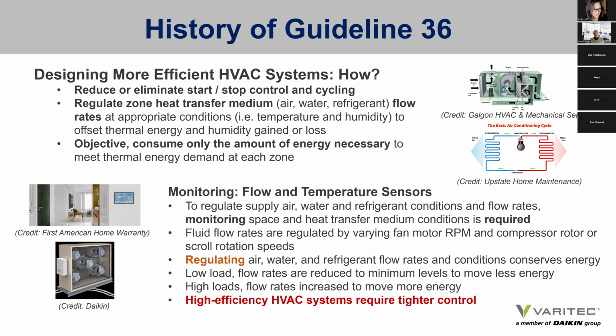You need to monitor the temperature of the space that could require cooling or heating, and you have to monitor the flow of heat transfer medium to those spaces so you don't overcool or undercool or overheat and underheat the zone. So to regulate supply air, water, and refrigerant conditions and flow rates, monitoring space and heat transfer medium conditions is required. Fluid flow rates are regulated by varying fan motor RPM, or fan motor speeds, and compressor rotor or scroll rotational speeds.